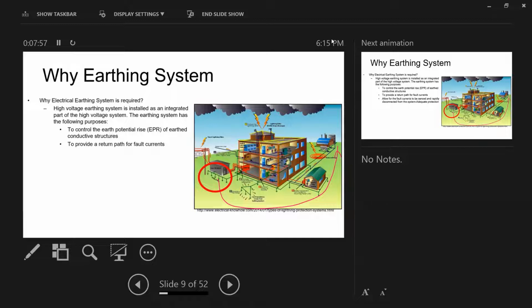So when there's a fault, for the current to go through, for those who are studying electrical engineering, they know we need to close the loop. If you don't have a closed loop, it must go back. If this resistance, guys, you inject 1,000 ampere, if this resistance in the ground is high, you'll have a massive voltage. Ohm's law always prevails. V equals IR. So that's why I need to design an earthing system made of soil and a conductor properly, to make sure my return path will not cause any high voltage or high potential along the way that could cause fatality.